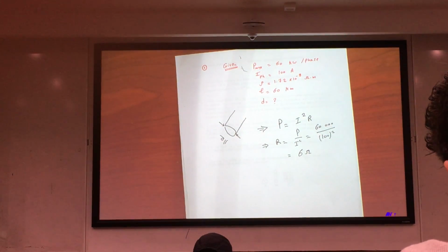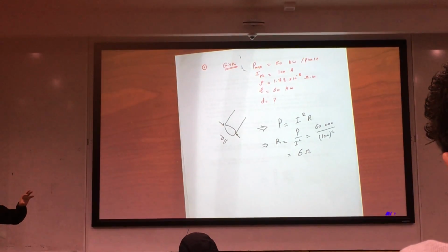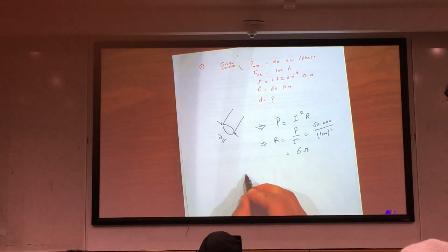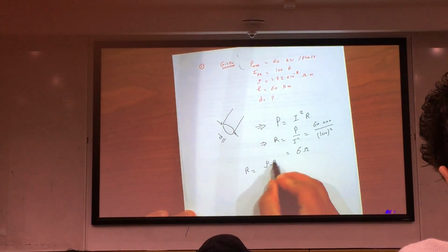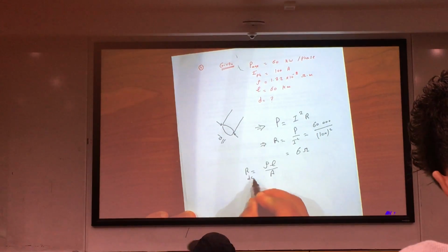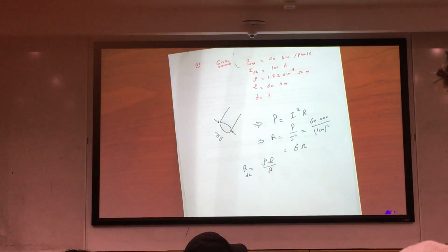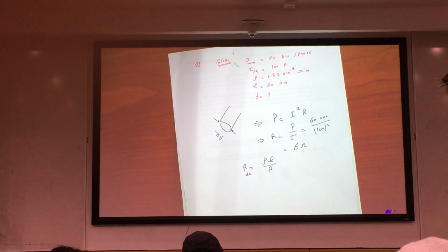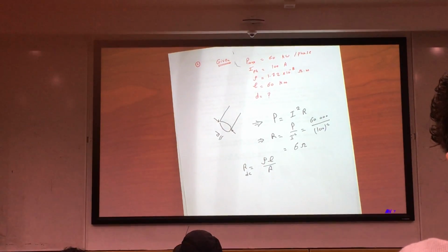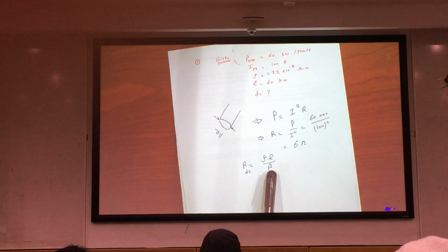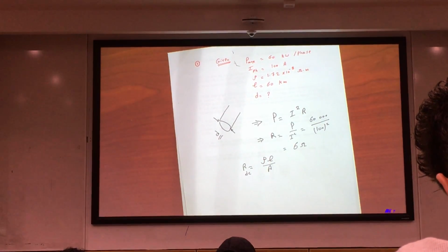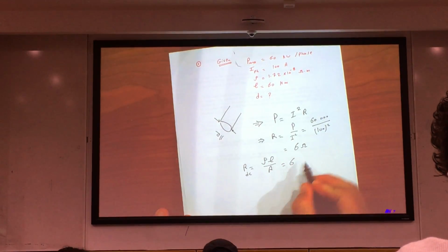And you know, this resistance has a formula we have taken in the lecture, that R is equal to rho L over A. I know we wrote that's R_DC, but there's not much difference between R_DC and R_AC. At 50 Hertz or 60 Hertz, the difference is very small and can be neglected. If you want to be more precise, you have to multiply this by 1.02 as we mentioned, right? But we can neglect this. So this will equal to 6 ohm.